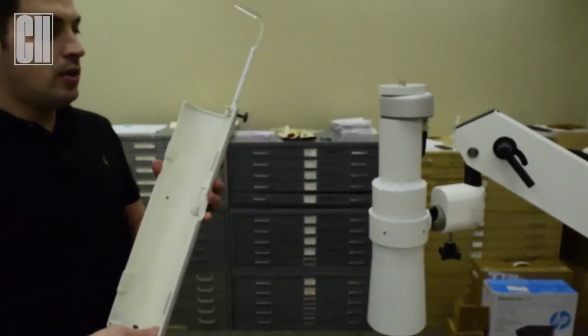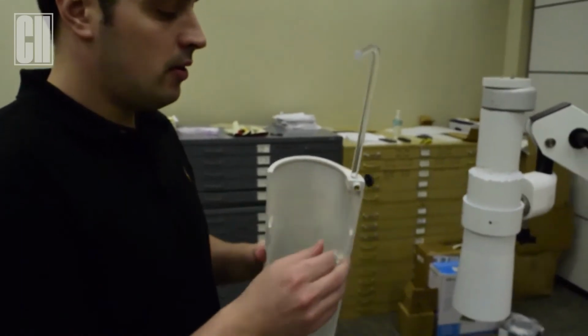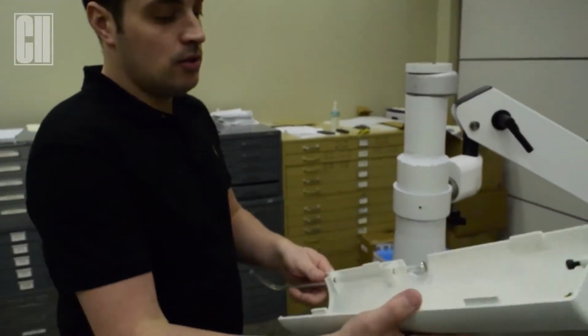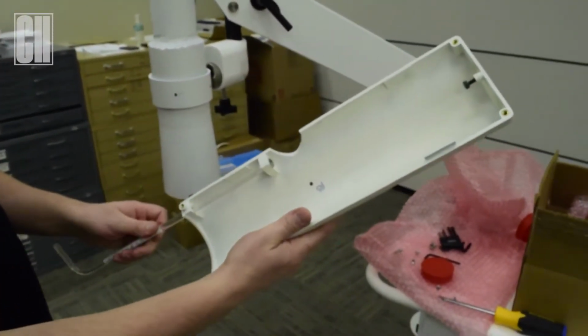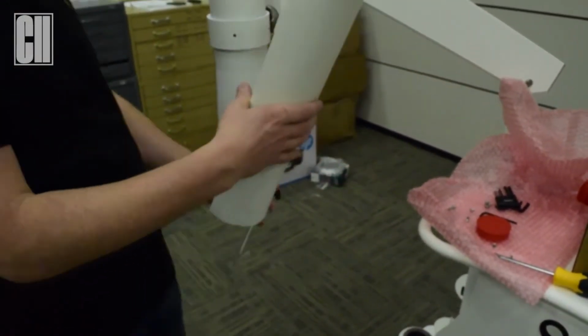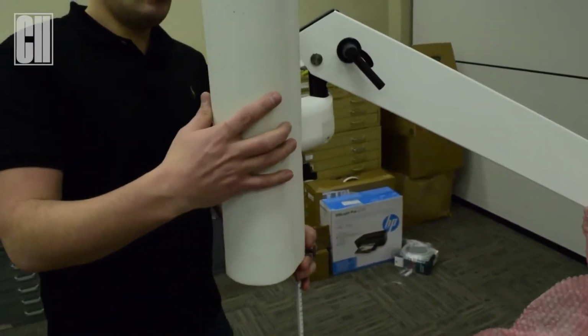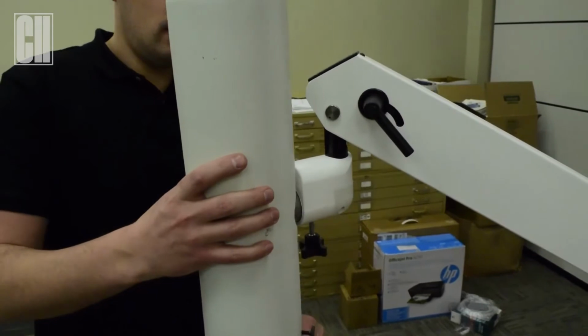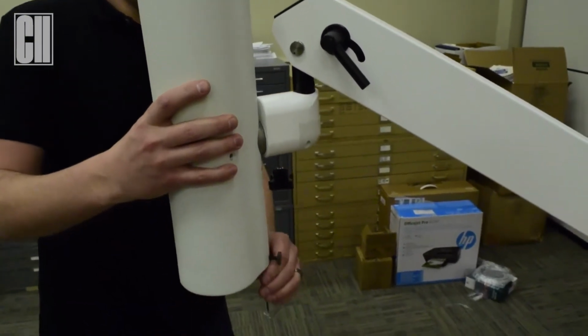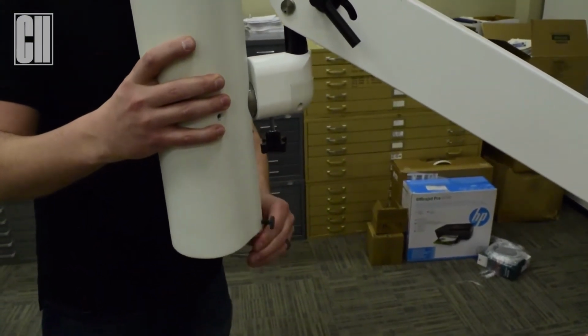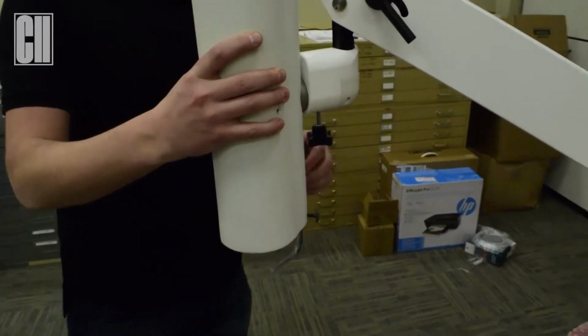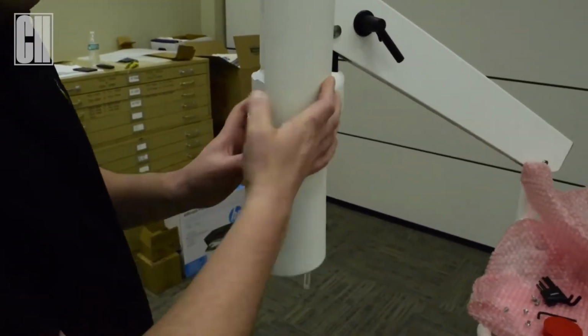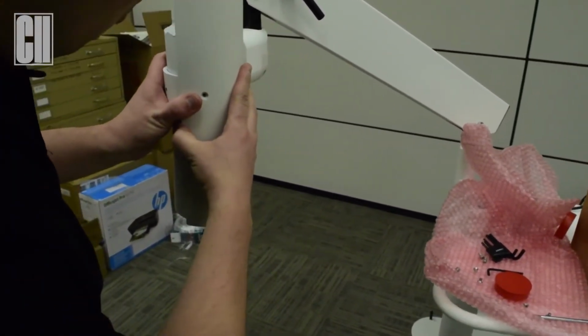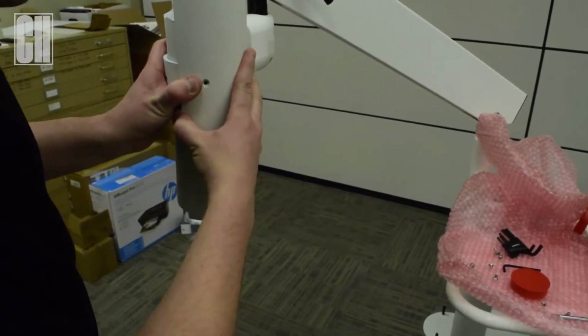You want to make sure that you put the side on with the pointer rod first. So you will pull the pointer rod down to the bottom to make it easier for putting it back together. Place the casing on, and then you push the pointer rod back up into the collimator. Once that's in place, you want to line up your screws, and we want to put in our Phillips head screws.